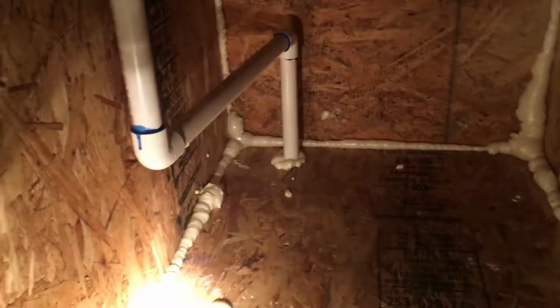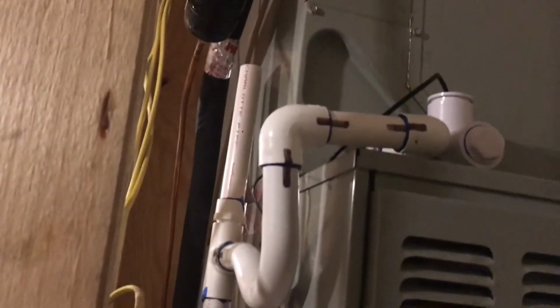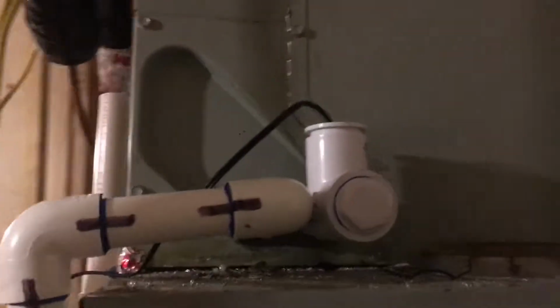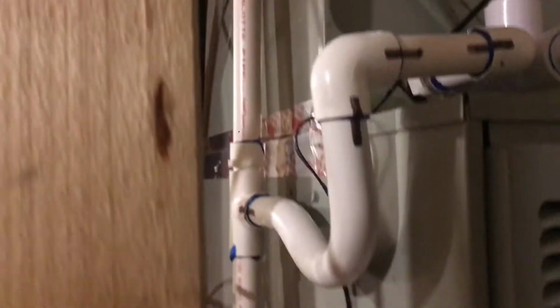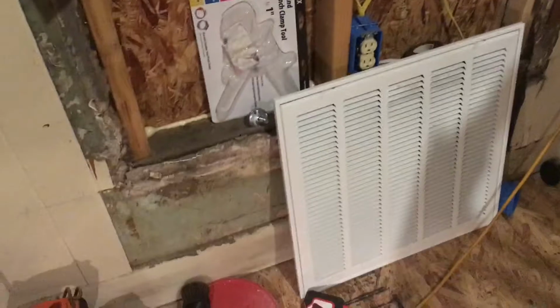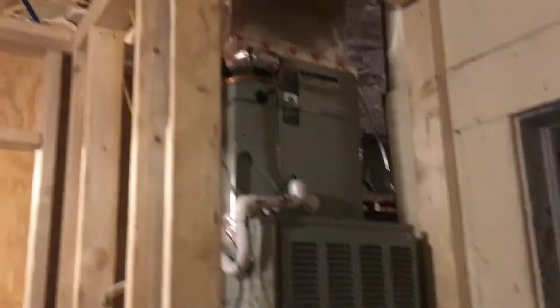And as you can see, I used the Great Stuff to seal this in as tight as I could, filled in every crack and gap and hole that I could find. That way this return box would be sealed and it won't be sucking unfiltered air in. There's my condensate line running up. Got a trap with a vent. Got my secondary float switch. Got everything all glued up. So all that's left to do is to put the return air grill on, put the filter in it, and then this system is all done and ready to be charged, which I'll do tomorrow.